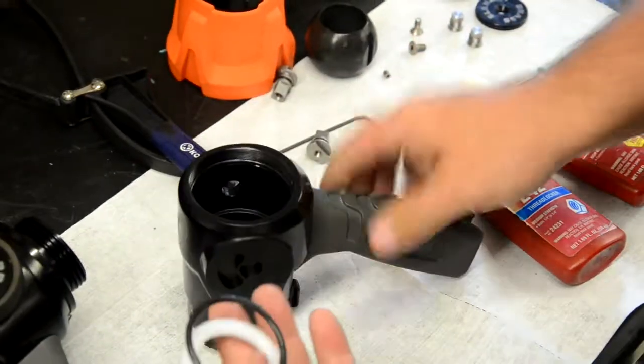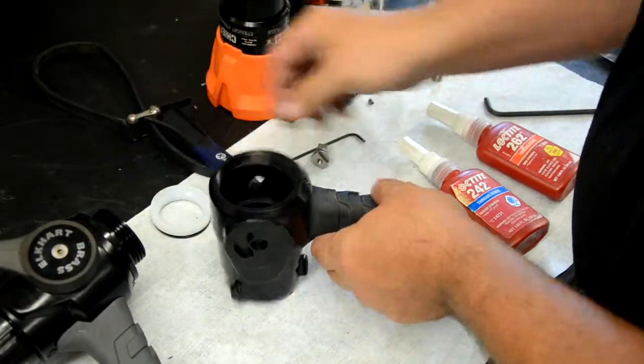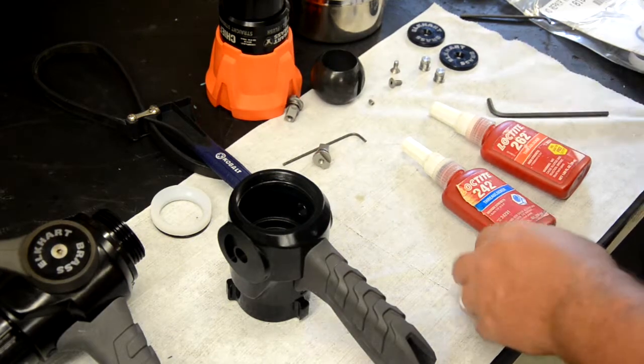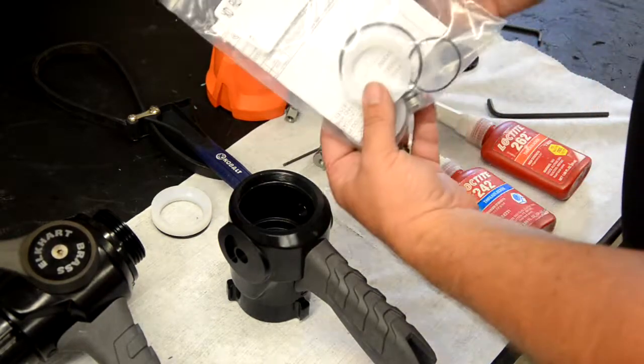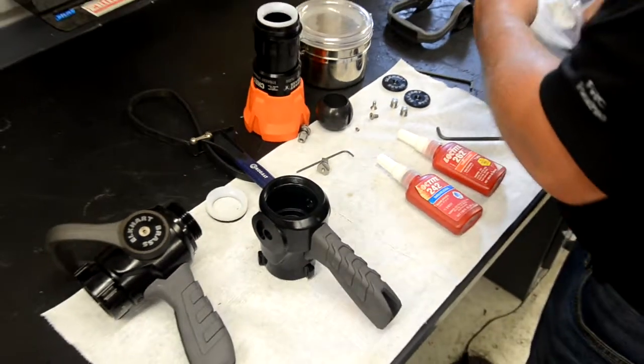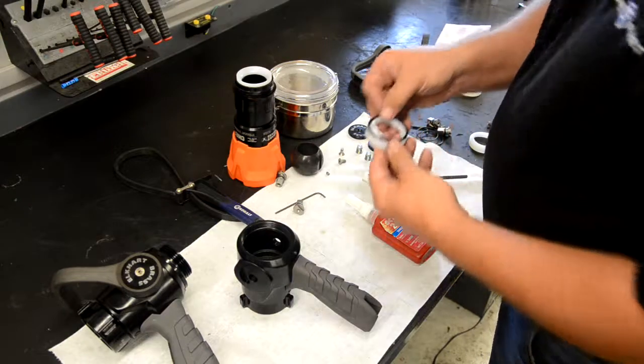With the bail handle removed, we can now remove the rear shutoff seat and remove that o-ring through the discharge side of the shutoff body. Go ahead and clean any dirt or debris you find inside the shutoff body and reusable parts. We're now ready to install the new parts from the XD Repair Kit. Be sure to lubricate all o-rings with Dow Corning number 7 silicone grease during installation.